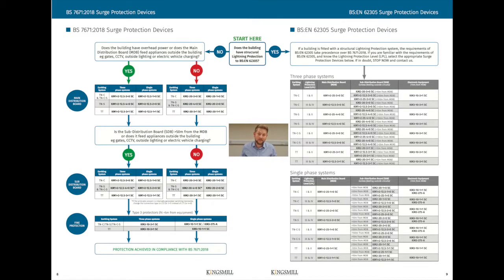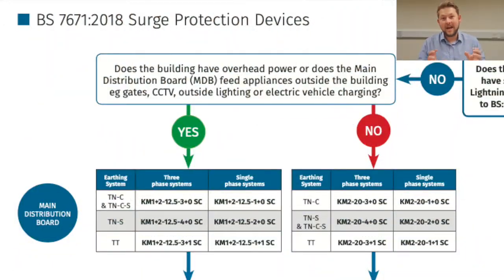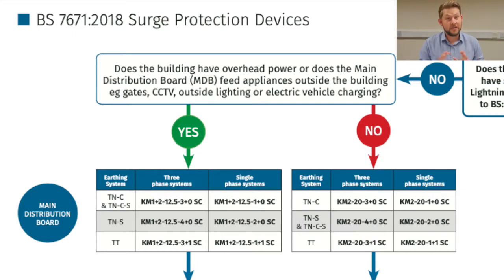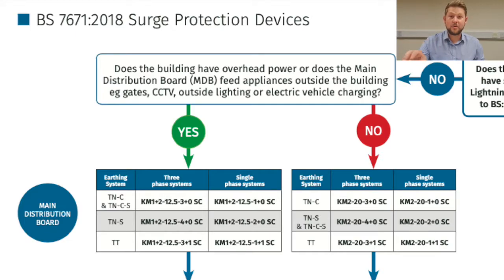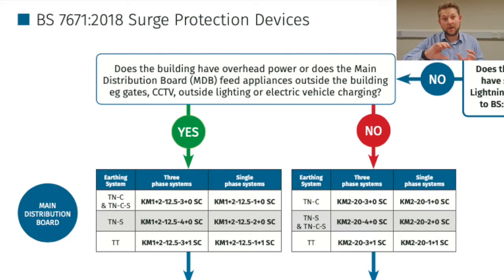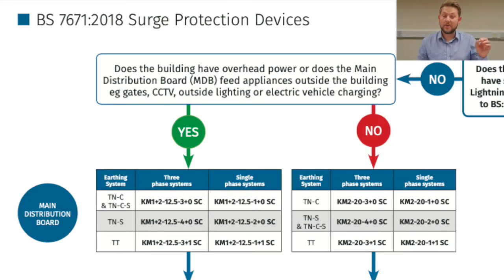If the building does not have external lightning protection installed, then we're looking at an 18th edition 7671 type device. For the main distribution board, we need to know whether the building is fed by an overhead power line, or if the main distribution board is feeding outside — for example, electric gates or EV charging points. If so, we're looking at a type 1 and 2 device. If not — so below ground, not feeding outside the building — then it will be a type 2.